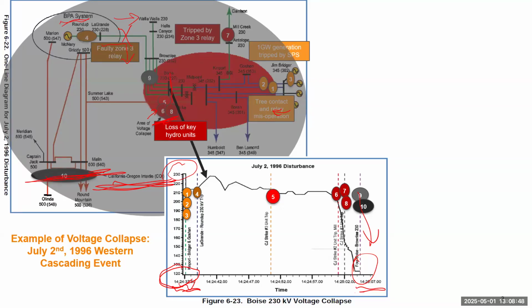All right, so there's no oscillation on the system because it's not caused by transient stability or undamped generator oscillations. It's mainly caused by a load area gradually losing the generation from outside, from internal, and then becoming weaker and weaker. Finally, the voltage cannot be supported.